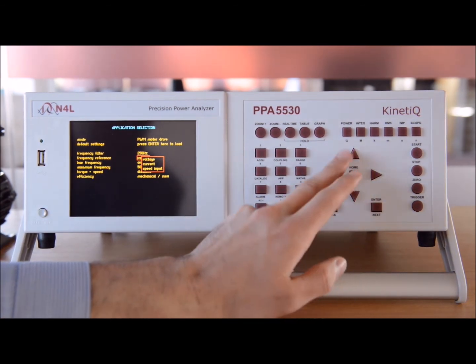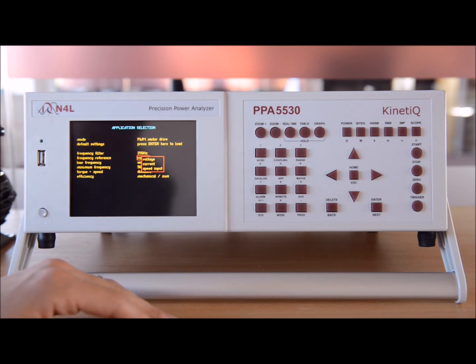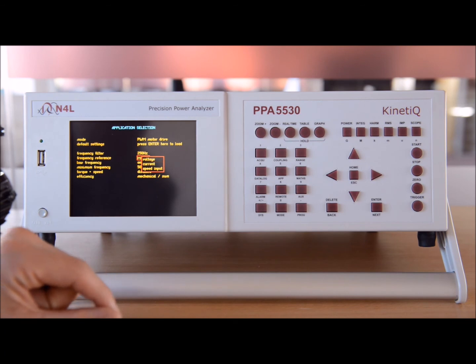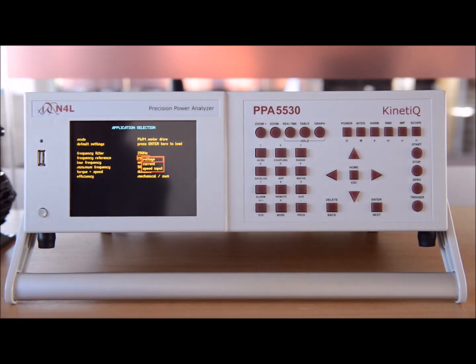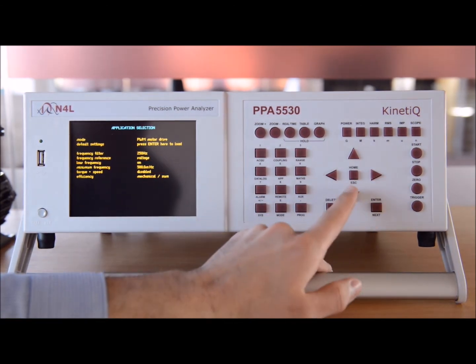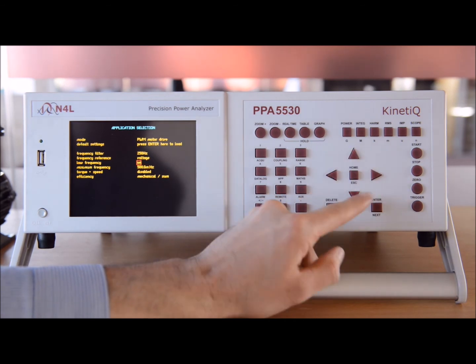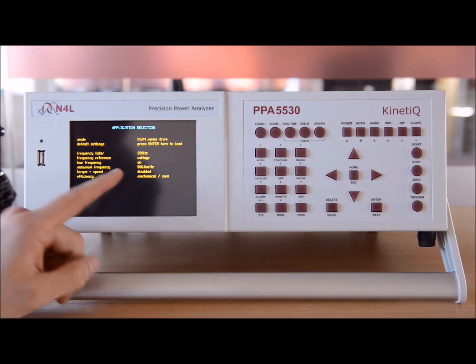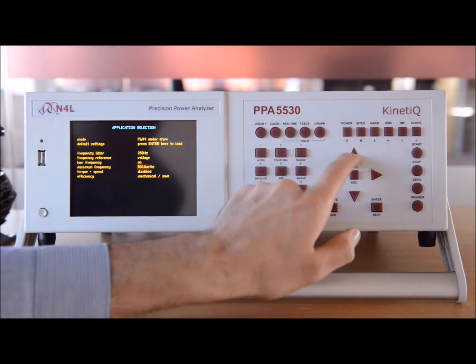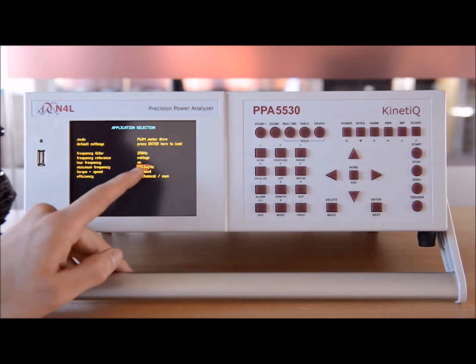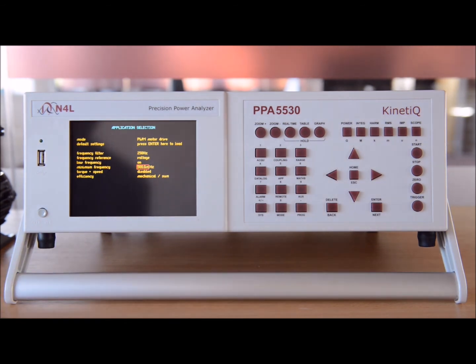Now we can choose to synchronize off the voltage and the current. The benefit of synchronizing off the voltage is that the voltage signal is always there, even when there's a very low current signal. So it's sometimes better with the intelligence of the parallel filtering option that we've got here to use voltage. We can also use speed, of course, from a speed transducer. And low frequency mode. Now this is a mode that sometimes confuses users, but what this means is that I've got here by default a minimum frequency which gets enabled when low frequency mode comes on, minimum frequency of 0.5 Hz. Now what that means is that the analyzer will continue to look for a frequency until the 0.5 Hz point, after which the analyzer will assume it's DC and show 0 Hz on the screen, on the display.